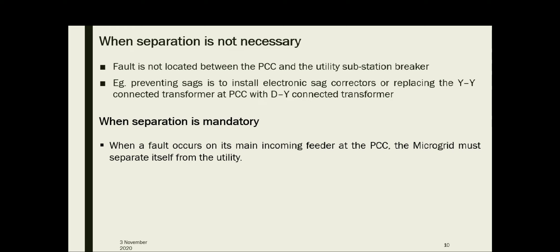The first case — when separation is not necessary — occurs when the fault is not located between the PCC and the utility substation breaker. For example, a fault causing sag on a substation bus may occur on an adjacent feeder fed from the same substation. In such cases, one option to prevent sag is to install an electronic-type sag protector, or to replace the star-star connected transformer at PCC with a delta-star connected transformer. For single-phase to ground faults, the utility delta-star transformer would ensure that the phase-to-ground voltage in the microgrid does not drop below 58%.